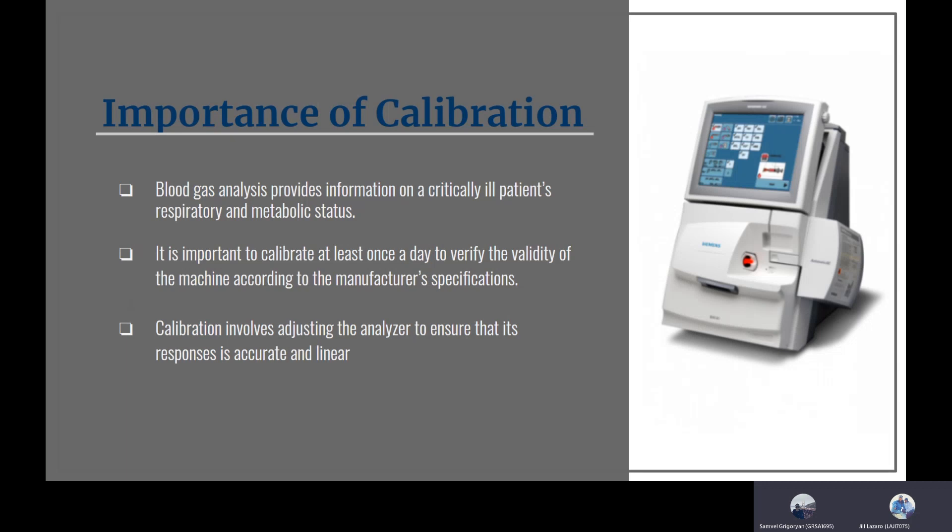Calibration involves adjusting the analyzer to ensure that responses are accurate and linear. We are getting essential information about our patients' measurements such as pH, carbon dioxide, PaO2, as well as electrolytes, lactate, and hemoglobin. We want to ensure that the measured values are equal to our known values, to make sure that what we're getting is accurate and representative of how our patient is actually doing.